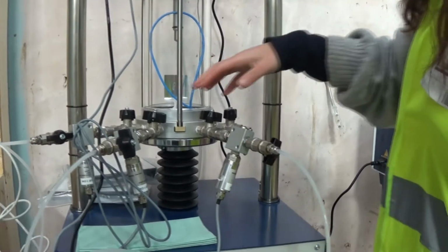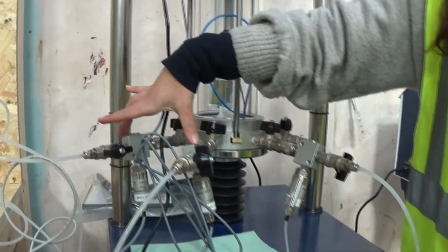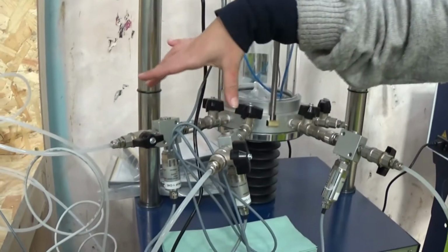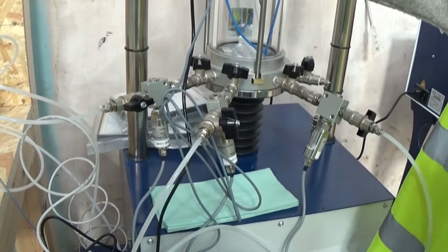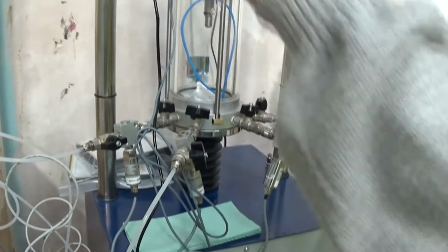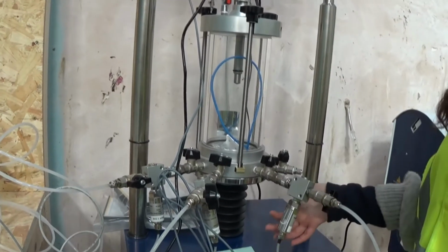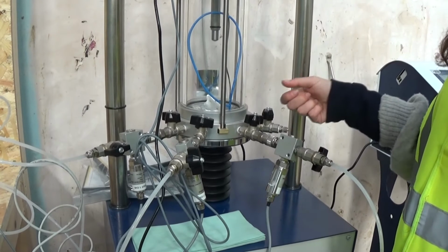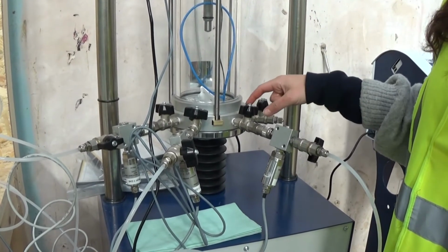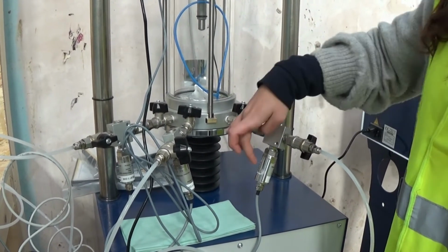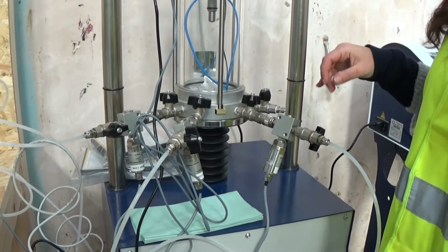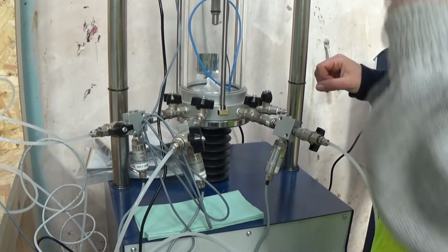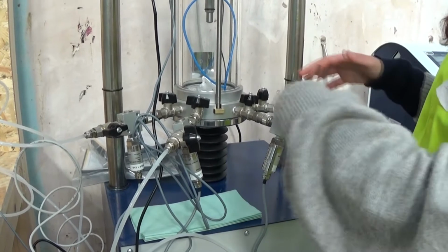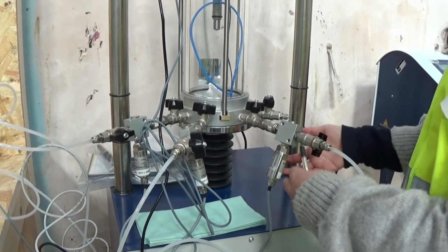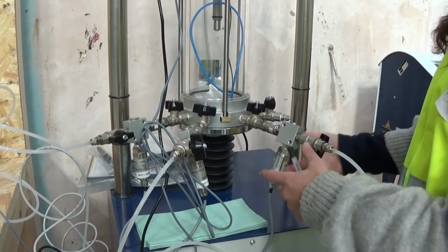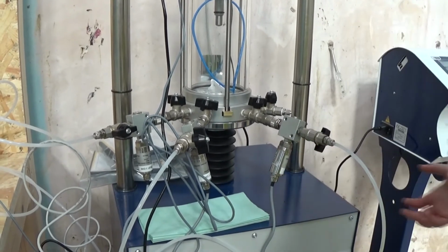The difference is that the cell pressure and back pressure have their line of pressure that you can see also in the panel. This is only a feedback of the sample. It means that this kind of transducer is only a reading of pressure inside the sample. You don't have to manage this pressure transducer. It's just a reading.